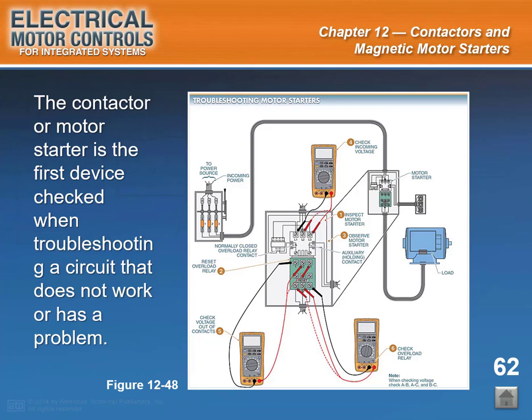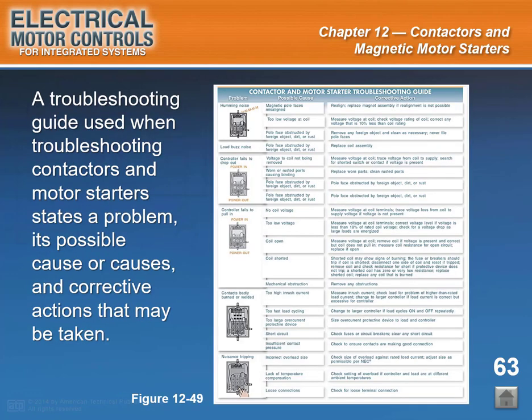Slide caption: The contactor or motor starter is the first device checked when troubleshooting a circuit that does not work or has a problem. See Figure 12-48. The power circuit and the control circuit are checked if the control circuit does not correctly operate a motor. The two circuits are dependent on each other, but are considered two separate circuits because they are normally at different voltage levels and always at different current levels. See complete procedural list on page 267. End of slide 62. Start of slide 63.